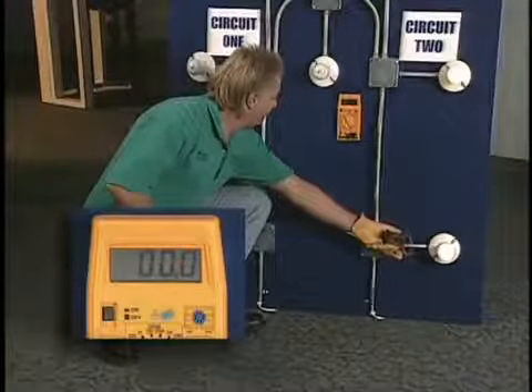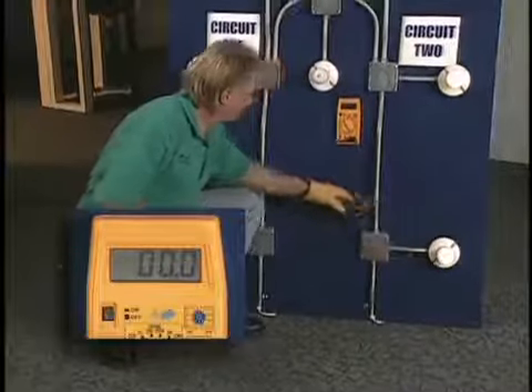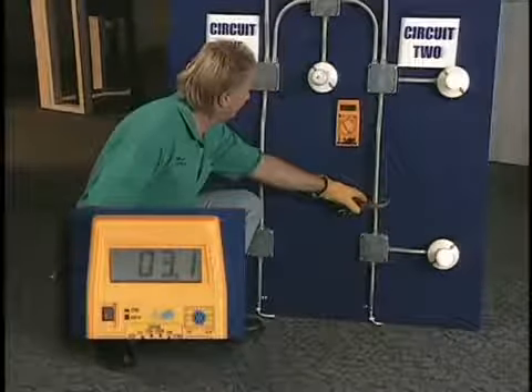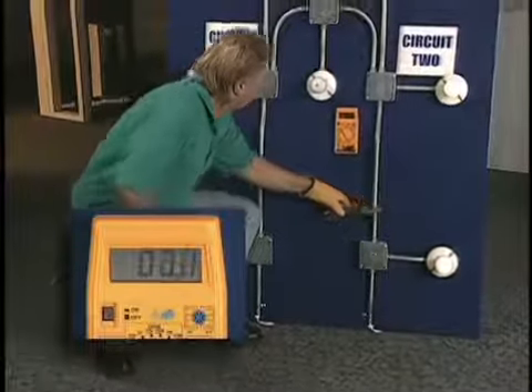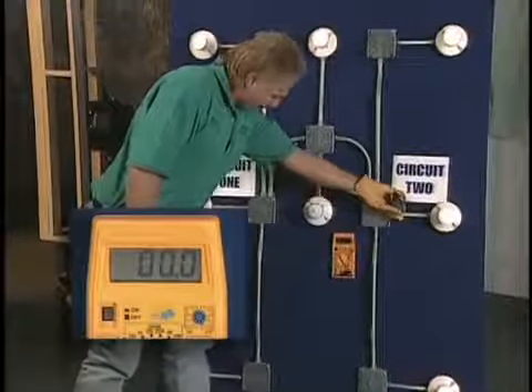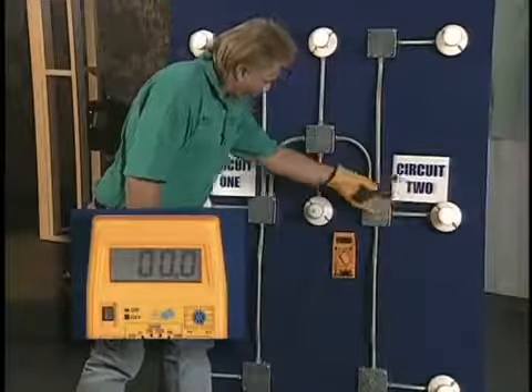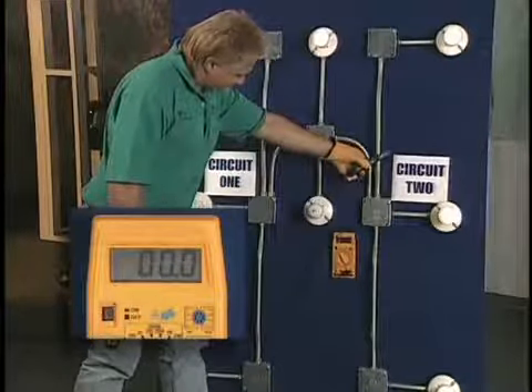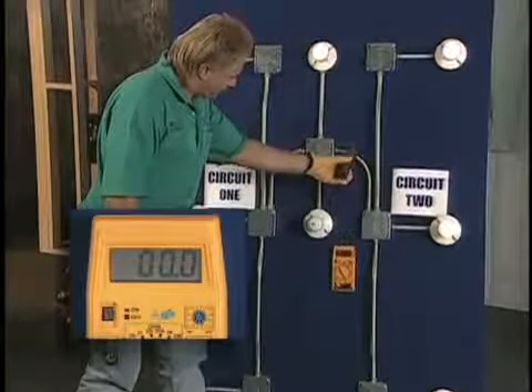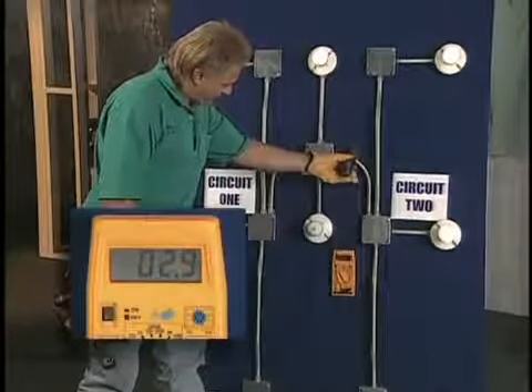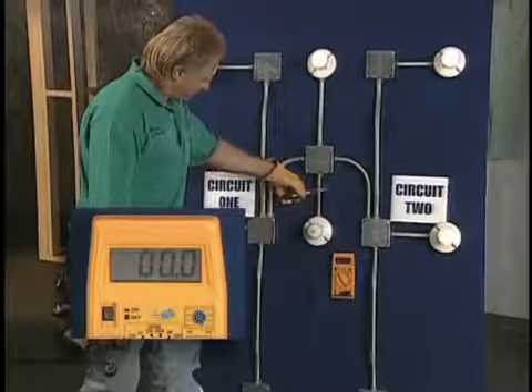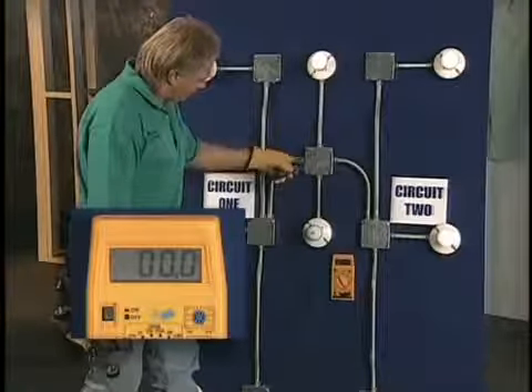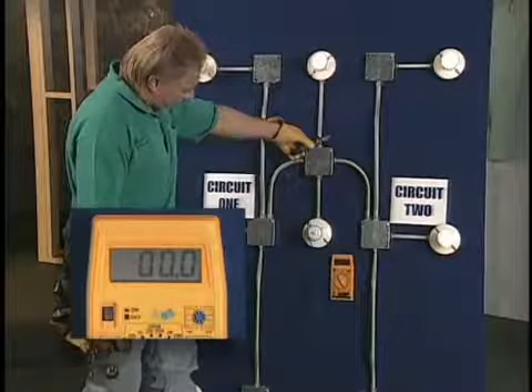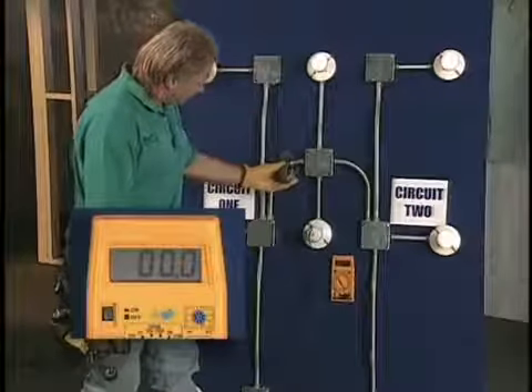Note which conduits carry the net current. Open it if you need to understand the connections inside. Otherwise, keep going. Watch the meter display as our electrician clamps onto the conduits. Follow the conduits with net current. Here we see that the net current leads us to a box with 4 conduits. Usually, the box you're looking for has at least 4 conduits. Open the box.